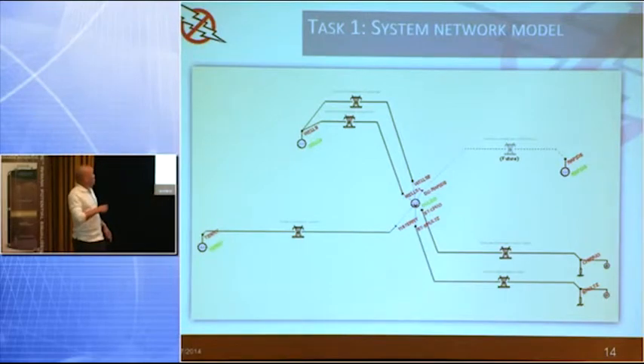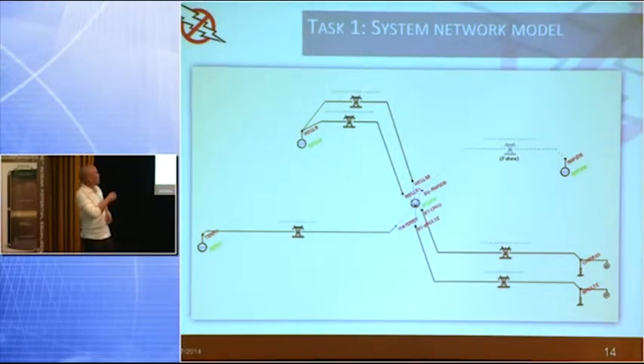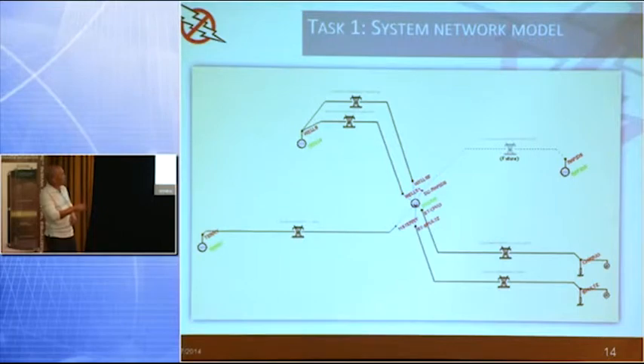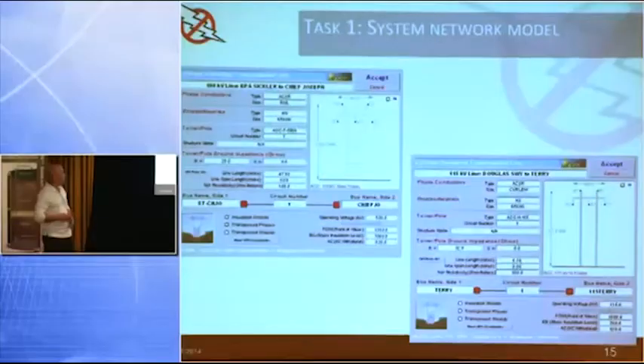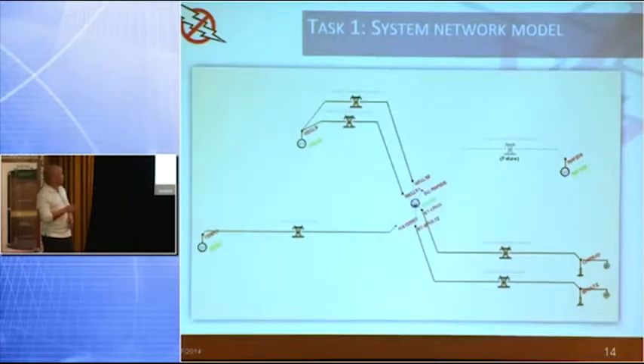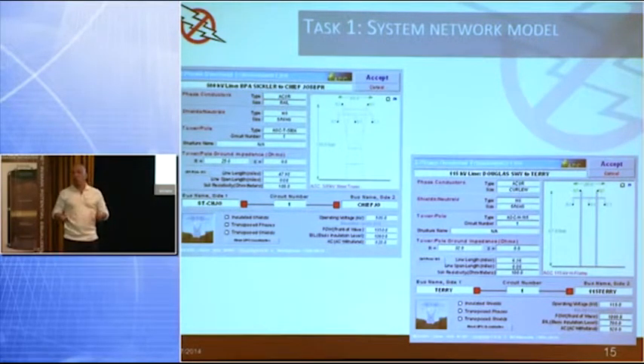What's represented here can be thought of as multiple resistors into the earth. So it's not just your grounding system here. We are talking about a complete system where these could be miles away from each other, and each one of these is another substation or the generation station. So you're starting to get an idea of the modeling capability, because we will go in and not only model just this facility, but if you clicked onto these icons, depending on the type of tower, even the type of shields and the steel and the type of conductor, that all has an impact on your overall impedance.